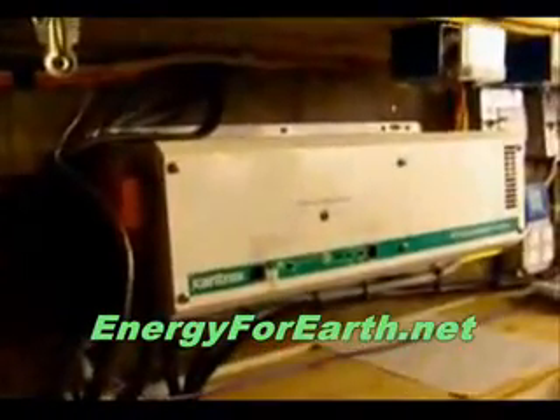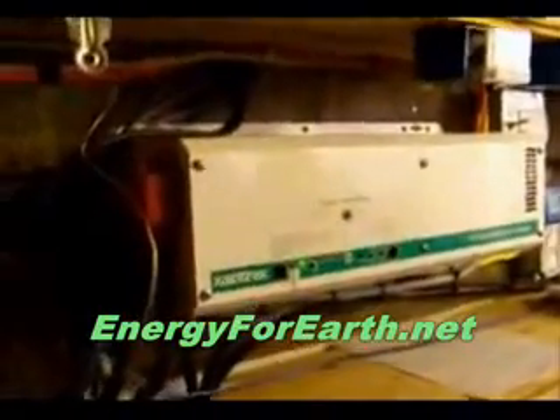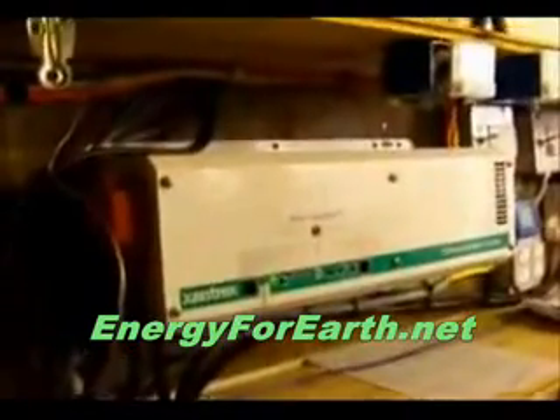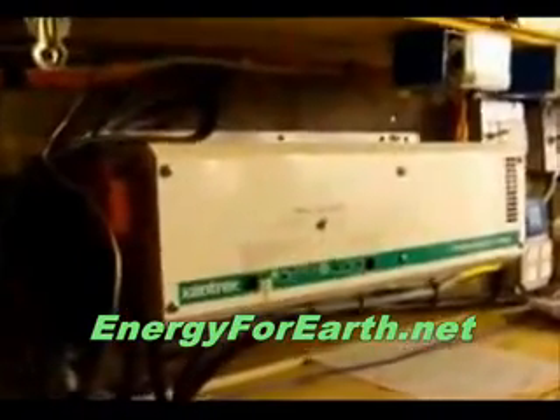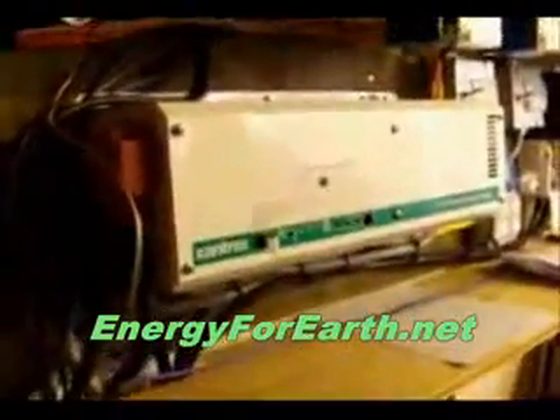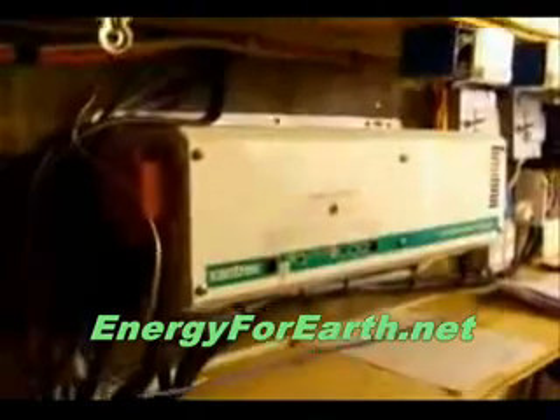Let me hit on this again: this is an off-grid system, not an on-grid system. Our off-grid system takes pure 12 volt battery power and turns it into 120, and we do not sell energy back to our utility company. If we were an on-grid system, this inverter would cost roughly 2 to 3 times as much, and we would need about 300 volts DC coming down from the roof to effectively make an on-grid system work for us. So for the cost of starting out, we decided to go with a strictly off-grid system.